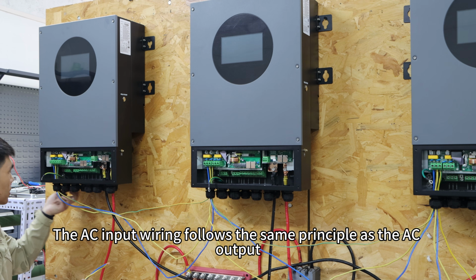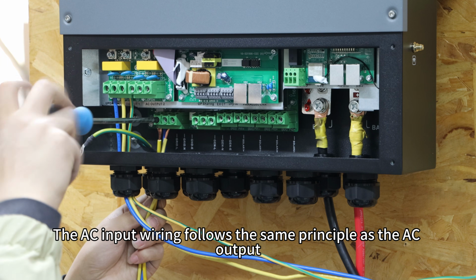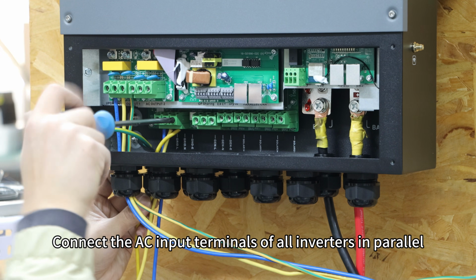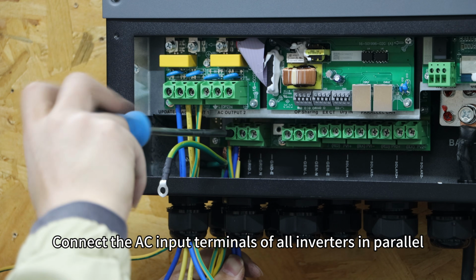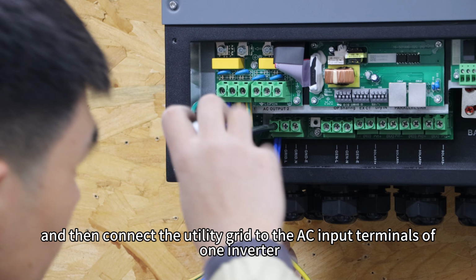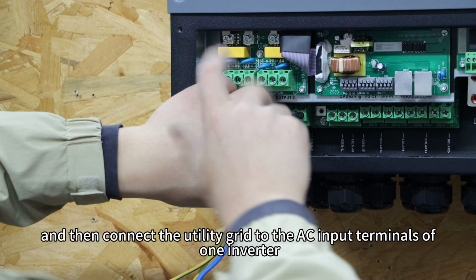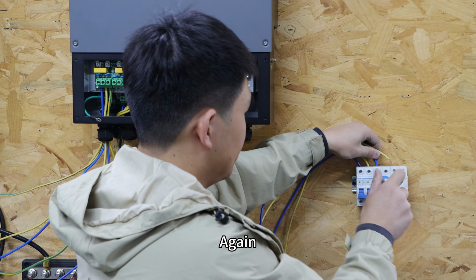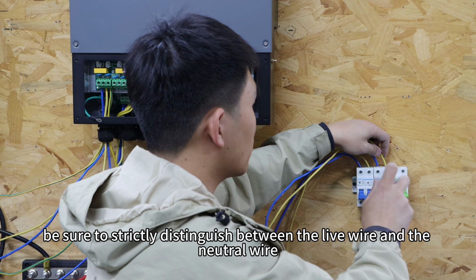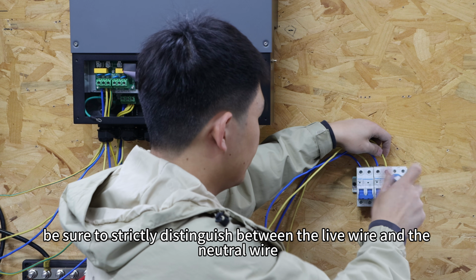The AC input wiring follows the same principle as the AC output. Connect the AC input terminals of all inverters in parallel, and then connect the utility grid to the AC input terminals of one inverter. Again, be sure to strictly distinguish between live wire and neutral wire.